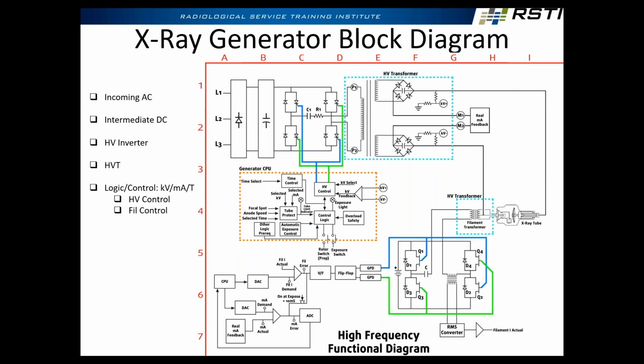What's the transformer's job? What's any transformer's job? Step up or step down? In this case, it's stepping up. So let's use some easy math and say that this high voltage transformer had a 1,000 to 1 turns ratio. If you were to cut open a transformer, what is it? A bunch of wires, right? It's coils. You've got a primary and a secondary, you've got input voltage, and you're going to step up or step down the voltage on the output side. So the job of the high voltage transformer is to just step up the voltage that was made by the inverter, okay? So let's use 80 kV as an example because that makes for easy math. And this was a 1,000 to 1 turns ratio.